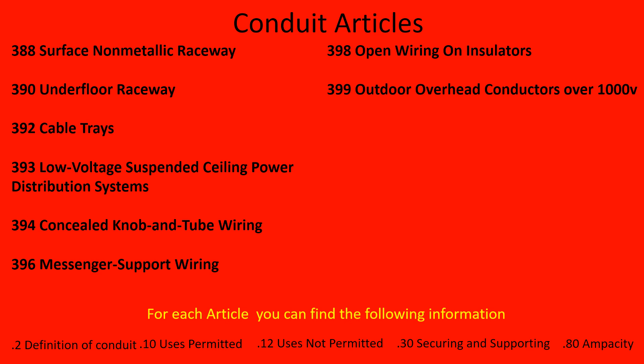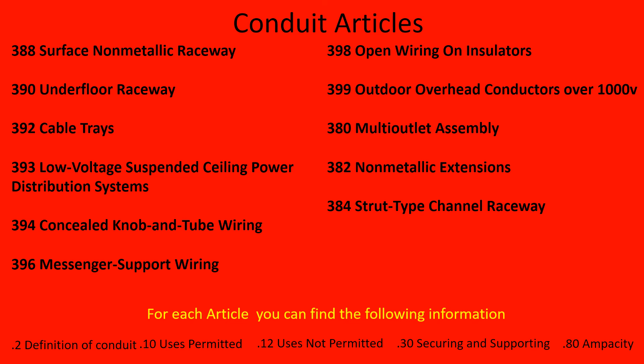And that wraps us up. Like I said for all the cables, it's super important that you go check this out — the dot two sections will give you the definition of that conduit, dot 10 will tell you where you can use it and in what manner, dot 12 will be the uses not permitted, dot 30 will be the securing and supporting, and dot 80 will cover any ampacity considerations if conductors are involved or it's a wiring method.